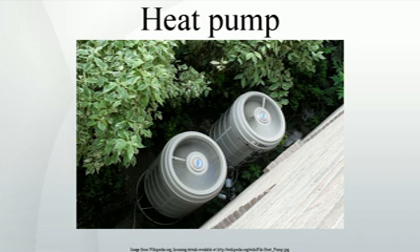Since 2001, carbon dioxide, R-744, has increasingly been used, utilizing the transcritical cycle, although it requires much higher working pressures. In residential and commercial applications, the hydrochlorofluorocarbon, HCFC, R-22 is still widely used, however, HFC R-410A does not deplete the ozone layer and is being used more frequently.